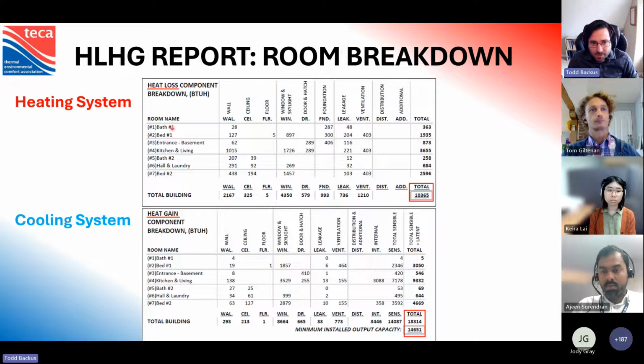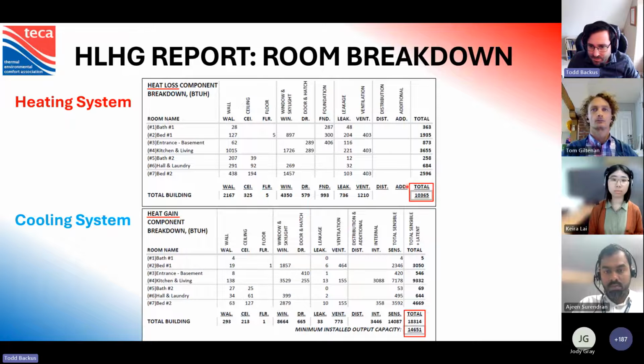So I have it broken down room by room, right? If we look at bedroom number 1, it'll tell you a value for the walls, for the floor, for the windows and skylights, the foundation, leakage, ventilation, and then it sums it up on the right. So you can look at what the performance of your building looks like from here. Typically you'll find that the windows are the highest on the heat loss. Often the walls are the next highest, and then you come into the foundation, leakage, and ventilation, and it all sums up over here.